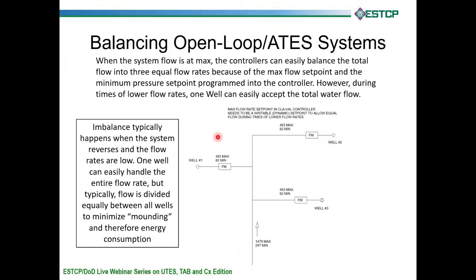But just to let everybody know, we have struggled with balancing of these systems at lower flow rates. At the max flow or at the design flow, it's no issue. But the farther you get down toward the minimum flow, the more out of balance it seems to get.